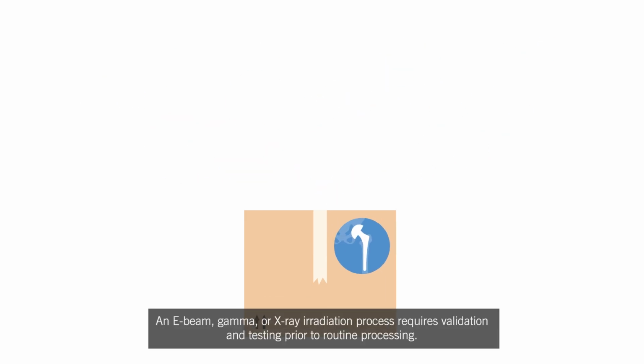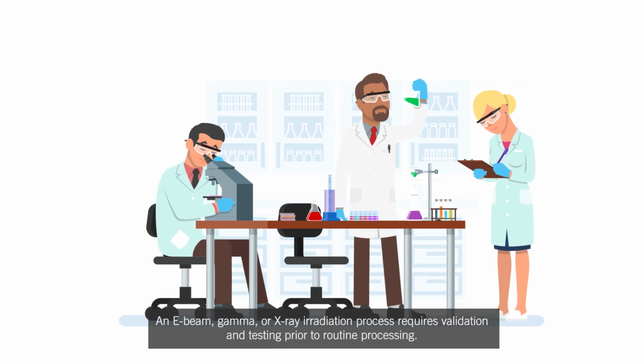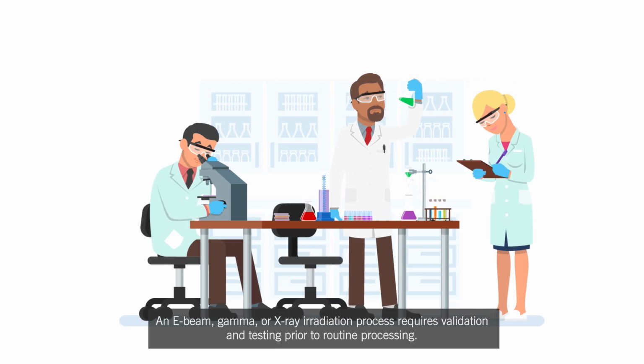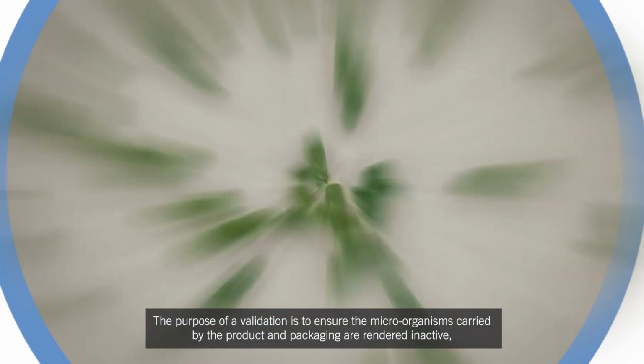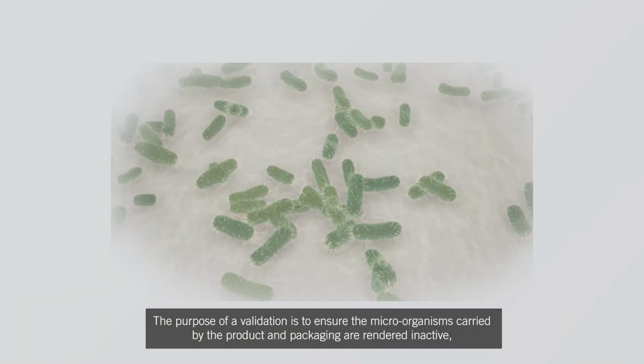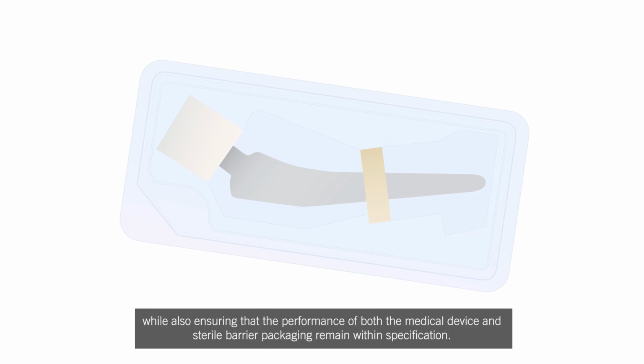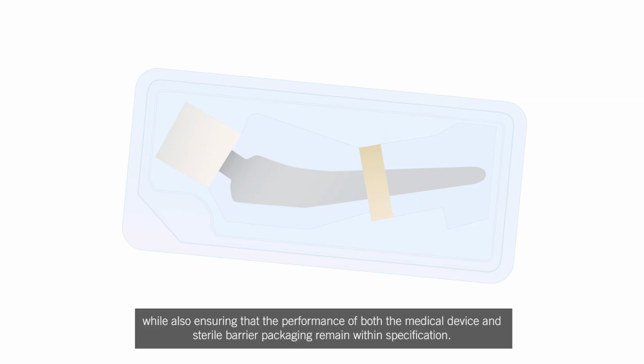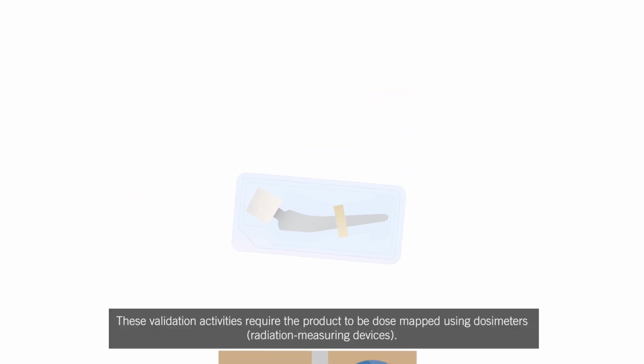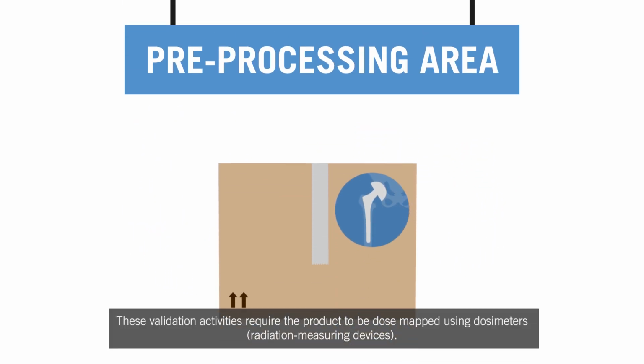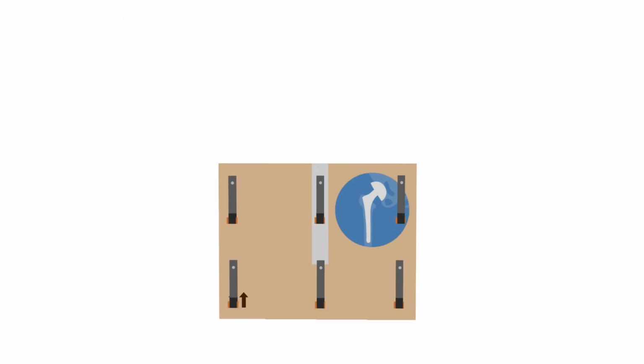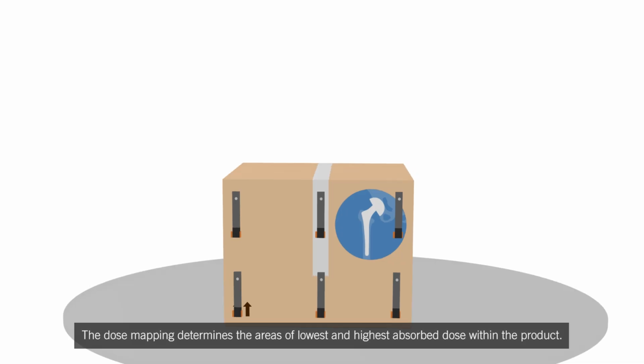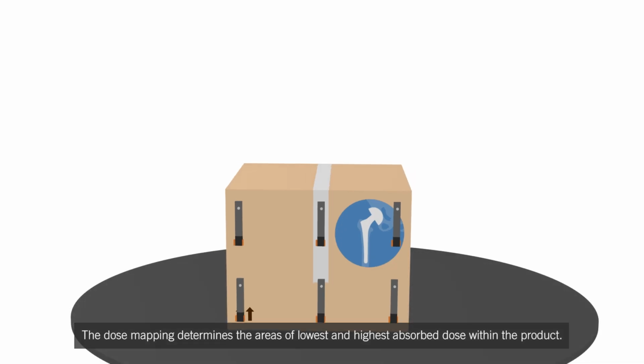An E-beam, gamma, or X-ray irradiation process requires validation and testing prior to routine processing. The purpose of a validation is to ensure the microorganisms carried by the product and packaging are rendered inactive, while also ensuring that the performance of both the medical device and sterile barrier packaging remain within specification. These validation activities require the product to be dose-mapped using dosimeters, radiation measuring devices. The dose mapping determines the areas of lowest and highest absorbed dose within the product.